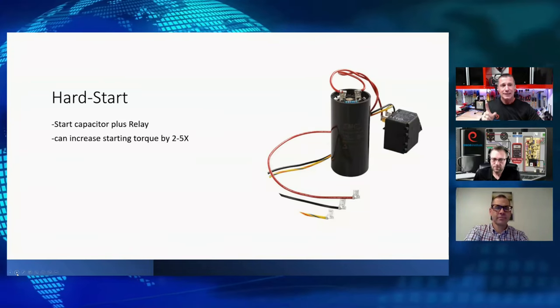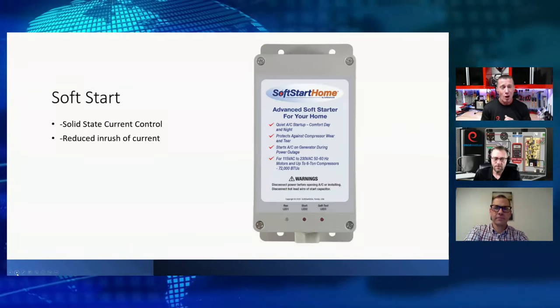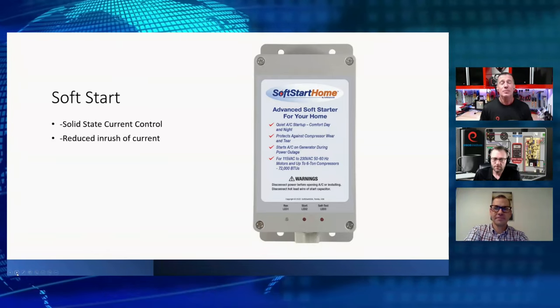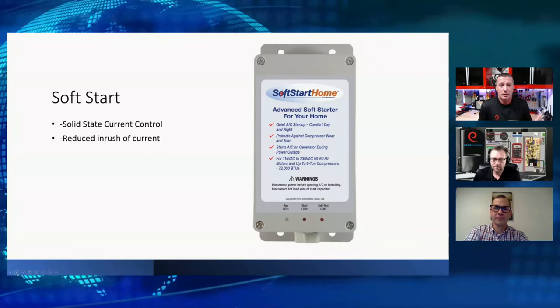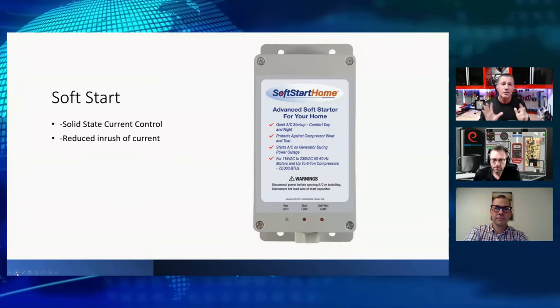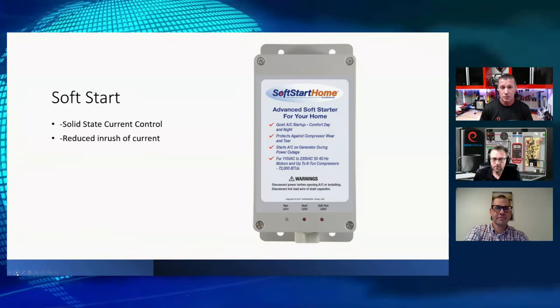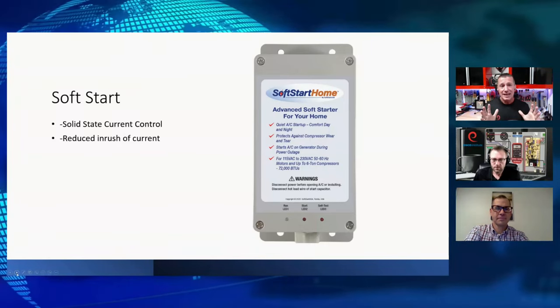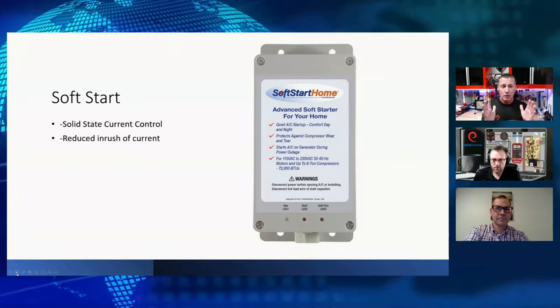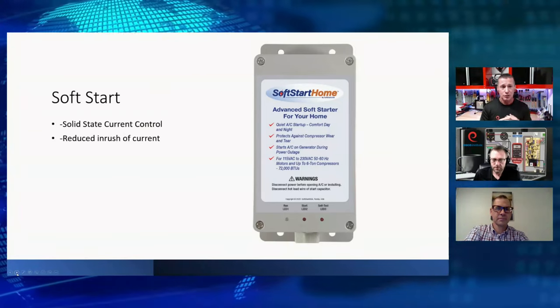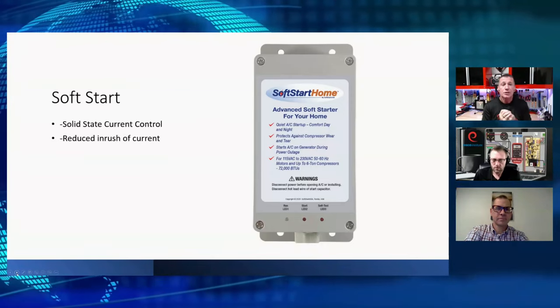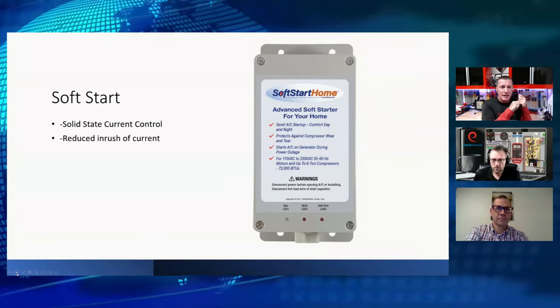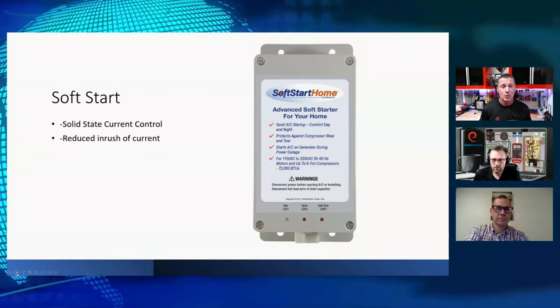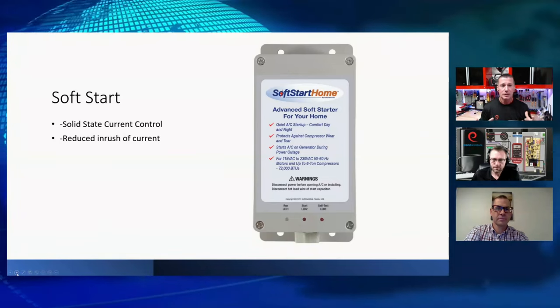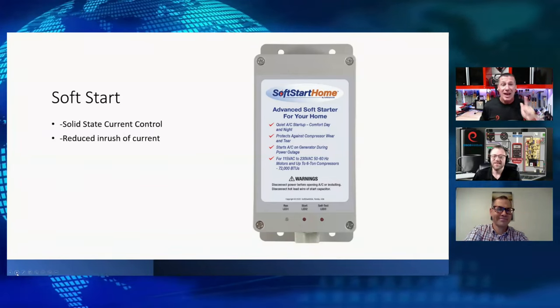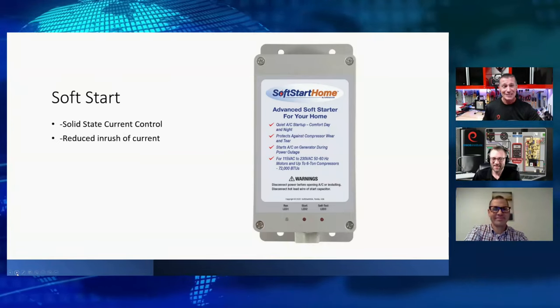But there's another one we haven't seen a lot of and we really have to talk about: soft start technology that can be utilized on permanent split capacitor driven compressors, PSC motors that are in our compressors. So what are we doing with a soft start control? We're taking a solid state control board and controlling the current that's being driven into the startup of our motor. We're grabbing hold of our current and controlling the way it's applied into our windings, into the phasing of our motor. What can we do with that? That's what we're here today to discuss. We're going to dive into what that looks like.